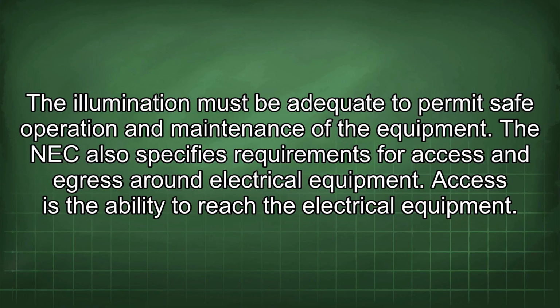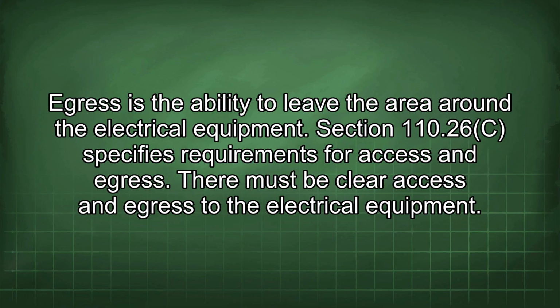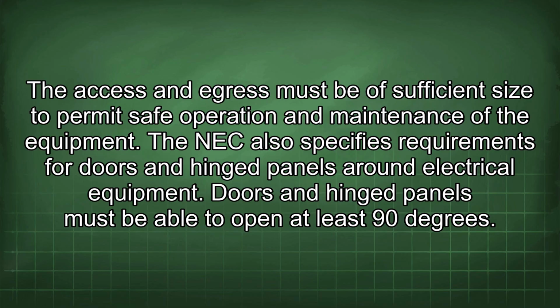The NEC also specifies requirements for access and egress around electrical equipment. Access is the ability to reach the electrical equipment. Egress is the ability to leave the area around the electrical equipment. Section 110.26(C) specifies requirements for access and egress. There must be clear access and egress to the electrical equipment. The access and egress must be of sufficient size to permit safe operation and maintenance of the equipment.